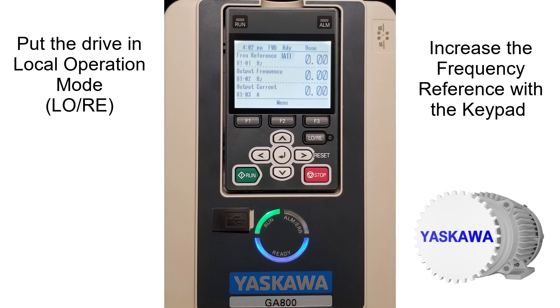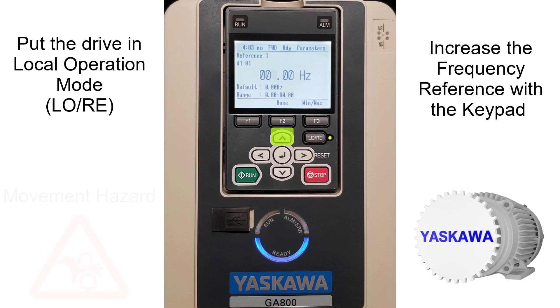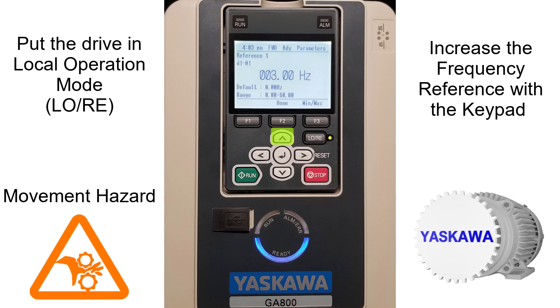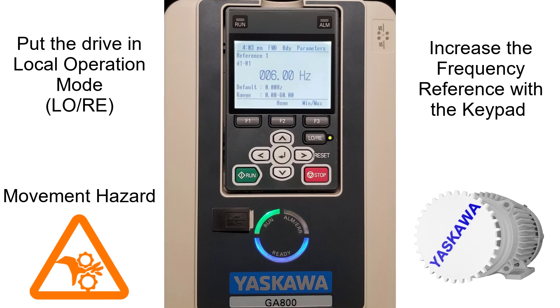Set the keypad as the frequency reference and run source by pressing the LORE key. The frequency reference source will change at the top of the keypad and the LORE key light will illuminate. From the home screen, press enter — this takes you to the reference 1 screen. Use the arrow keys to enter a frequency of 6 Hz, press enter, then press run. The drive run light should go solid and the motor will spin.